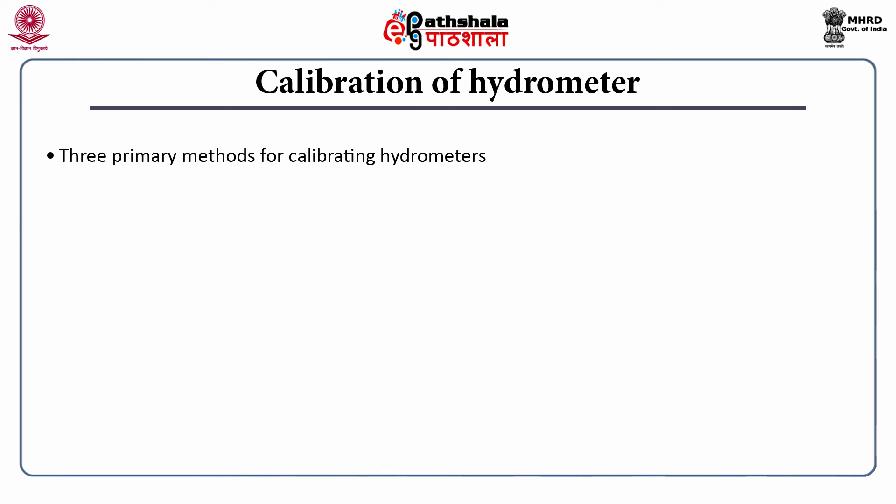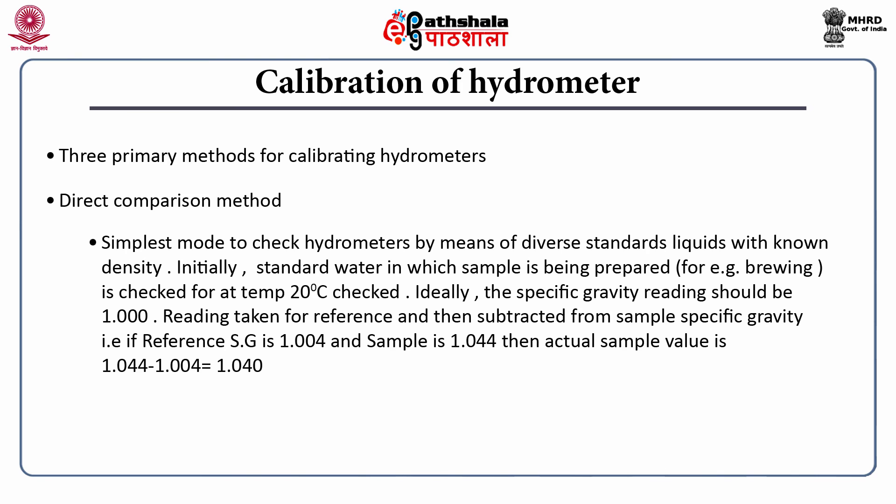Coming to various methodologies for calibration of hydrometer, there are three primary methods. The first is the direct comparison method, which is the simplest — checking hydrometers using a standard liquid with known density. This is generally done with standard water first. If you are in the alcohol industry, the basic standard water is checked at 20°C. Ideally, the specific gravity reading should be 1 at 20°C. The reading taken for reference is then subtracted from the sample specific gravity.